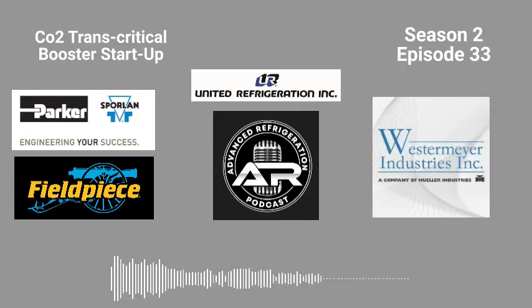And then what I'm going to do is shut the low temp pumps off, and I'm going to start charging the flash tank. I'm going to leave the medium temp liquids off. All the liquids are going to be off at this point. And I'm going to start dumping into the flash tank. Go ahead. Liquid just out to the cases is off. The rest of the liquid feeding the liquid injection, that's still going to be running, obviously, right? That's off usually. You won't need it. If you're just charging a flash tank, the vapor's going to be so cold off that you're not going to need it. So what I do is start charging the flash tank and start getting everything in there.